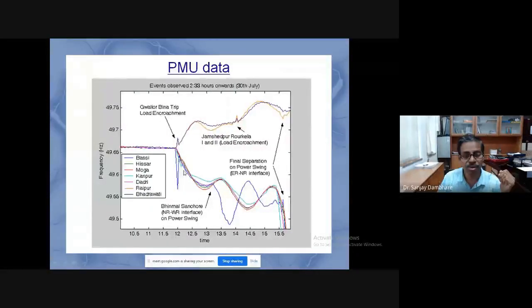You can see that the system was not subjected to a fault, but this major line, the Gwalior to Bina line, was tripped on load encroachment, and the distance relay could not identify that it was load encroachment and not a fault. This major corridor was lost, and the load on that corridor shifted to some other transmission lines, which created a swing also.